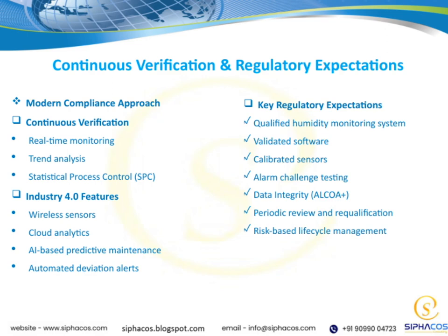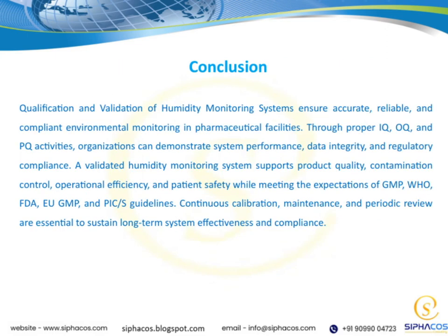To wrap up, qualifying and validating humidity monitoring systems is key to keeping environmental monitoring accurate and reliable in pharmaceutical settings. By completing installation, operational, and performance qualifications, we prove the system works as intended and meets regulatory standards. A validated system protects product quality, controls contamination, boosts efficiency, and safeguards patients. It also aligns with guidelines from GMP, WHO, FDA, and others. But it's not a one-time task. Ongoing calibration, maintenance, and reviews are vital to keep everything running smoothly over time.